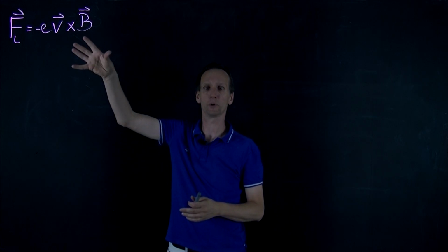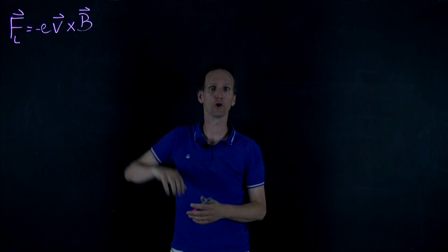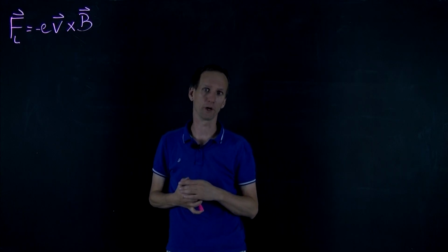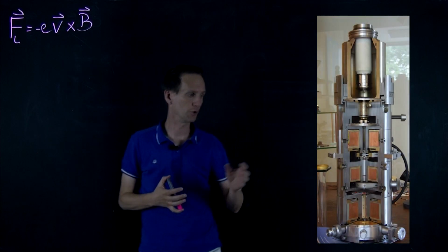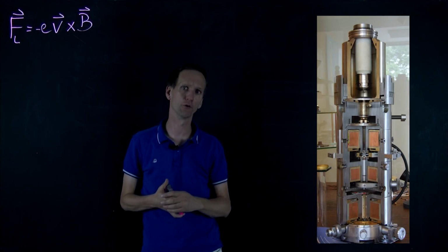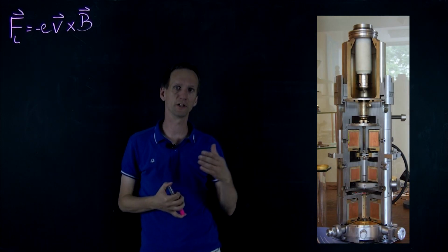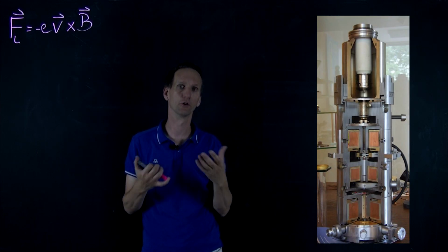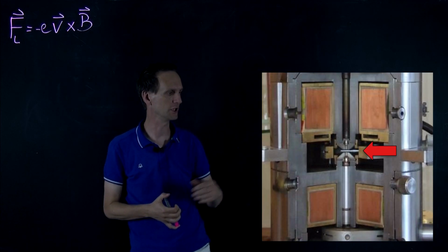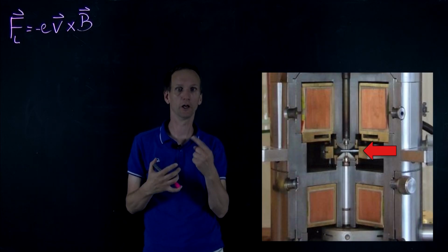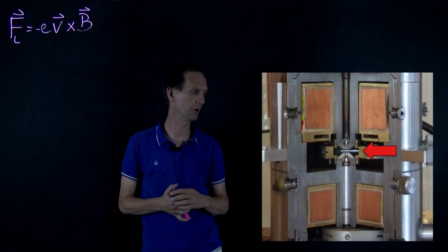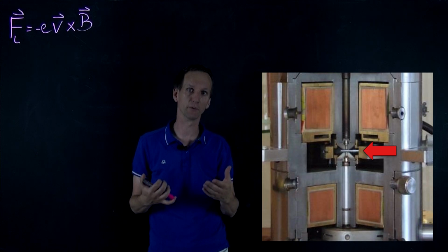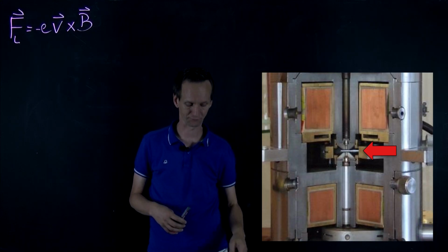So also here we play a special trick by applying a non-homogeneous magnetic field. Actually, magnetic lenses are often encountered in electron microscopes, more often than electrostatic lenses. Here you see a photo of a cut-through of a transmission electron beam column, where you can see the copper wires of the coils surrounding magnetic material that brings a magnetic field to the optical axis. Here you see a zoom-in, where you can clearly see the individual copper wires, and you can see that in this case the sample holder is in between two lenses.